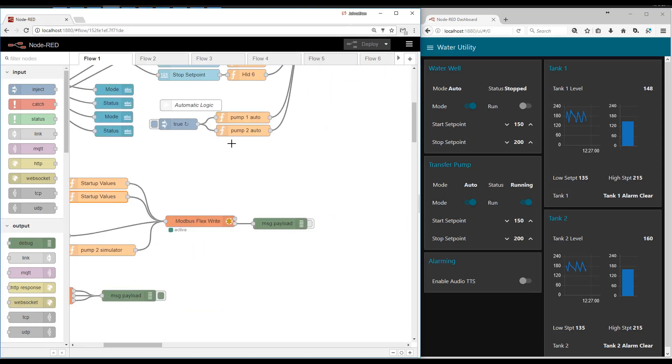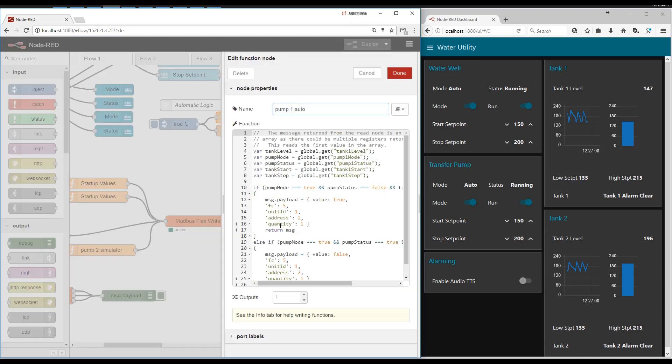And then here's the automatic logic. If mode is set to auto, looks at the tank levels. And if the tank levels reach the criteria, it will read and write to the Modbus register to start and stop the pump.